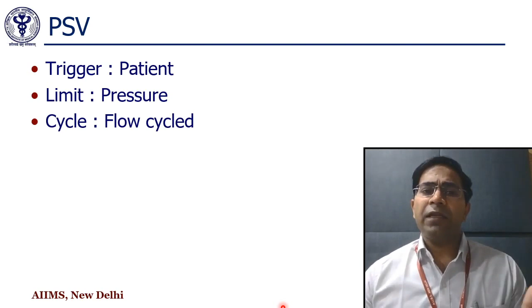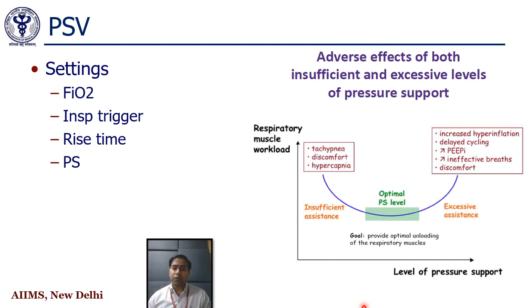In pressure support, it is flow cycled. If you talk about the settings, we have to keep some inspiratory trigger. As we all know, we can keep it around 2. Then is the rise time. For the rise time, now we all know that this angle should be around 80 to 90 degrees. And then is the pressure support. We keep pressure support to deliver a particular tidal volume, and there are also certain concerns about the pressure support.